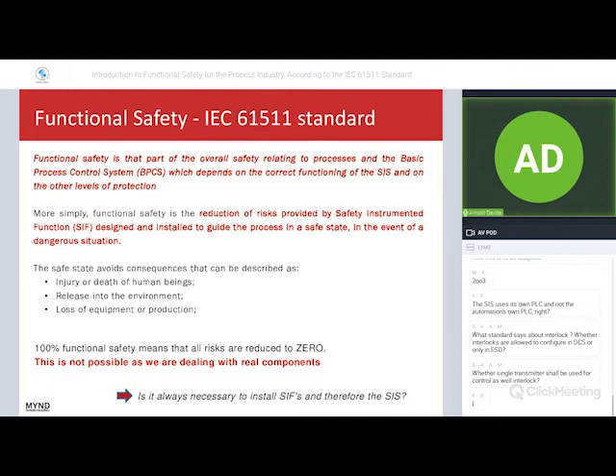If, for example, we have a failure of the BPCS, we have to install a safety instrumented system in order to drive the process to a safe state before the dangerous event. The safe state avoids consequences that can be described as injury or death of human beings, release into the environment, or loss of the equipment or production.